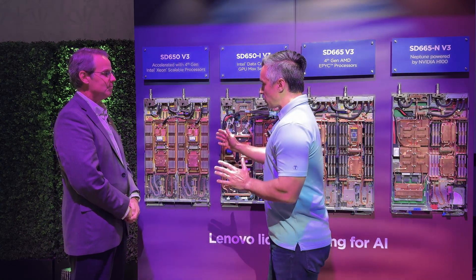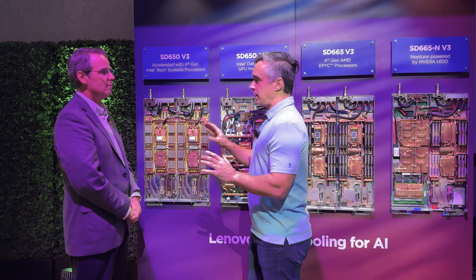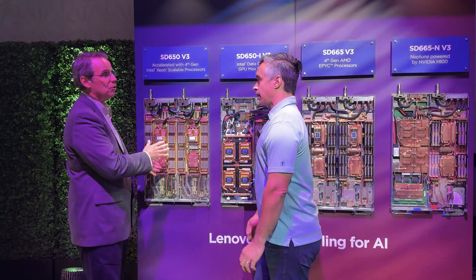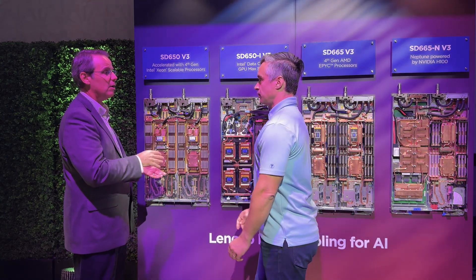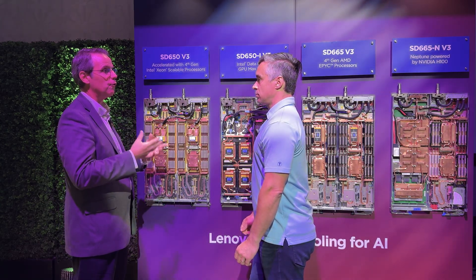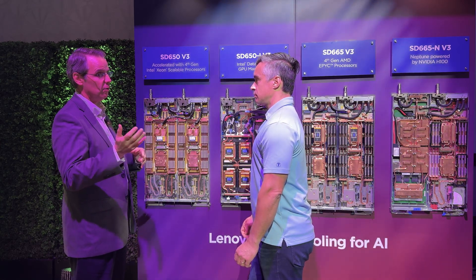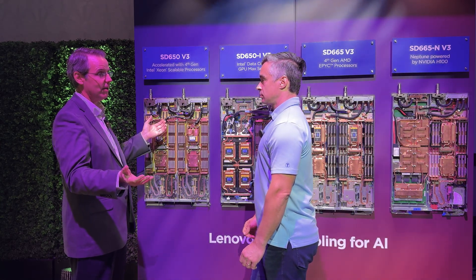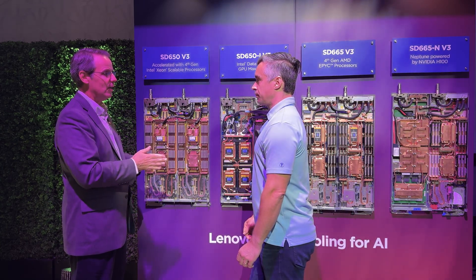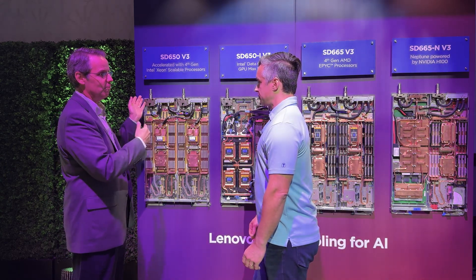These are fully liquid cooled — we've got no fans in here of any kind. So we're going to have a major power savings. Actually it's closer to 30% — 30% of any data center's electrical power is used for fans. And that's money spent moving air from the front of the rack to the back of the rack, basically two or three feet. It's not calculating data, not storing data, not moving data — it's just moving air three feet.